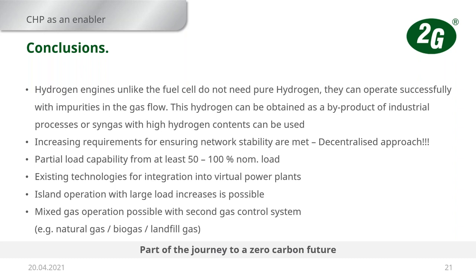Okay, that's great. Thanks. To an extent, does that help progress the technology ahead of piped hydrogen supply? Well, the applications we've been looking at for this are temporary installations, where they wouldn't need piping up, because there's no hydrogen infrastructure at the moment anyway. So you end up with an engine being delivered, and a hydrogen containerized storage solution being delivered. The container with the hydrogen storage would have all the gas in it to drive the engine. Then it's a case of how much density of hydrogen you need inside that storage vessel, and how long you want to run the generators for.